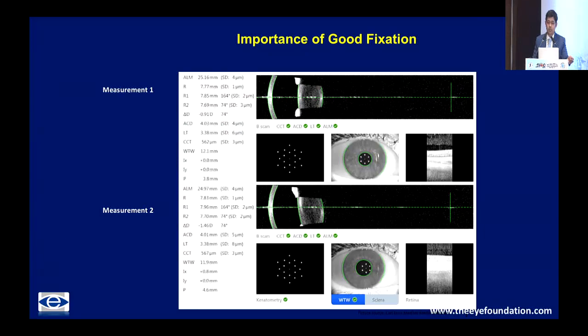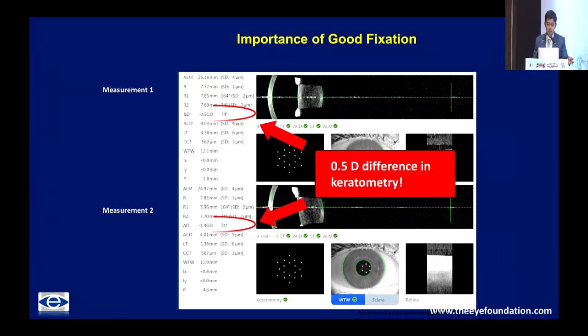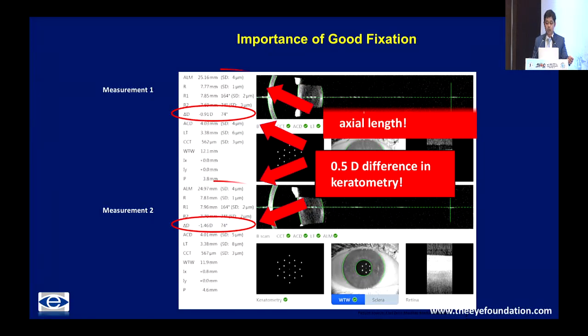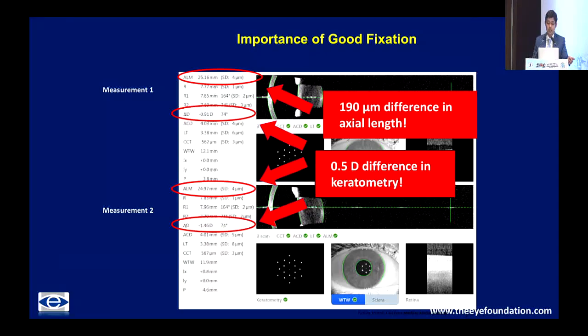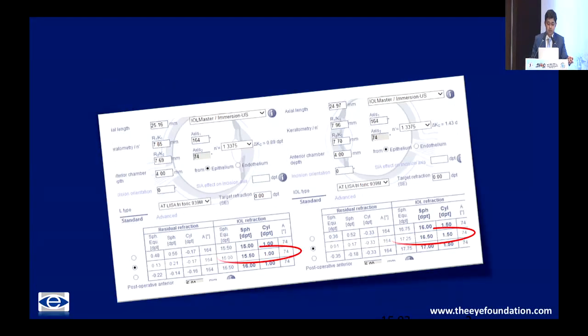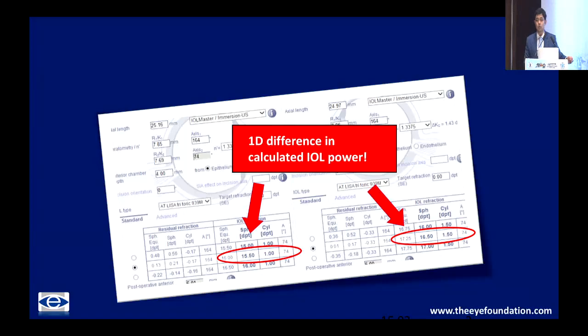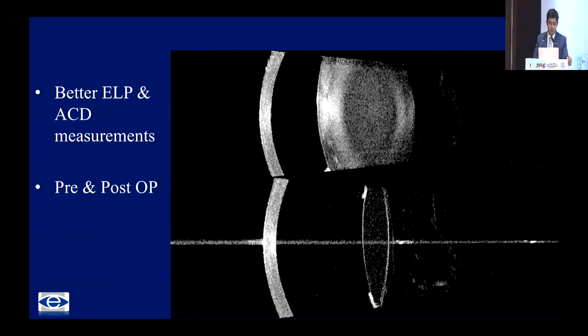Whereas in this particular image, you can see that the foveal pit has not been imaged correctly, and this leads to a significant difference in the keratometry. Even if it's just a 0.5 diopter difference and a 190 micron difference in axial length, it gives more than a diopter of difference when it comes to IOL power calculations. So it's very important that we ensure that the patient is fixating, and now we have a device which is actually telling us whether the patient is fixating properly or not.